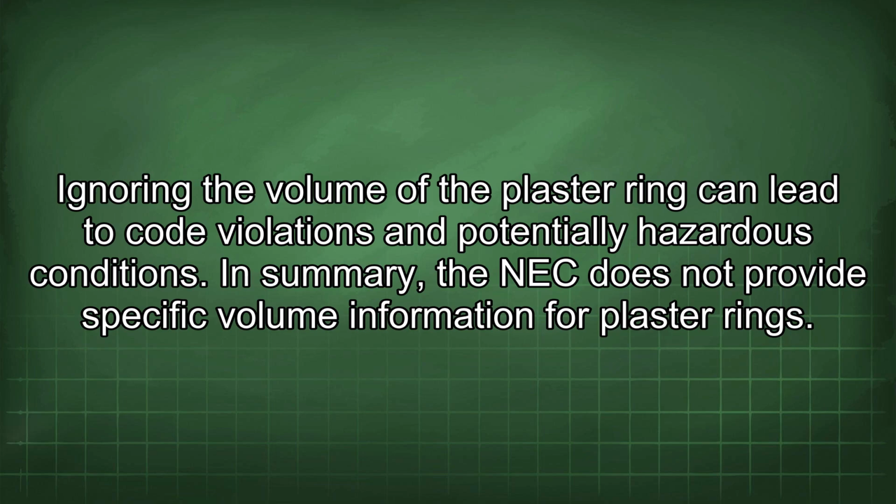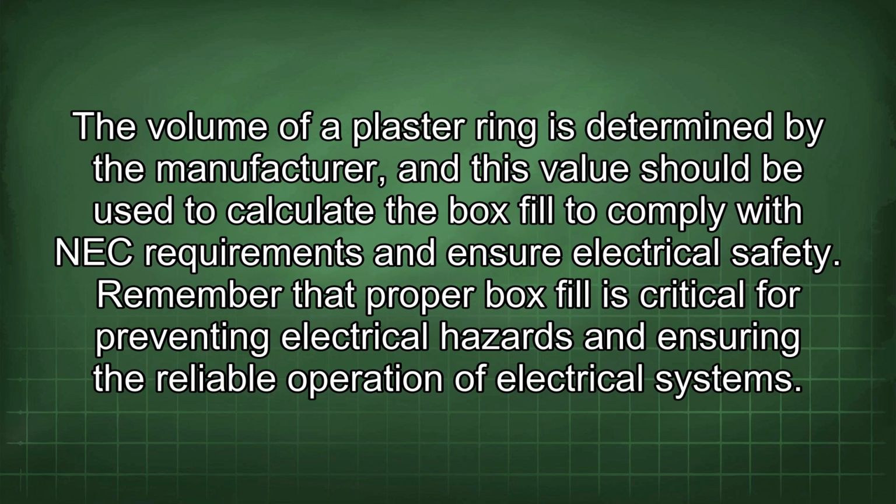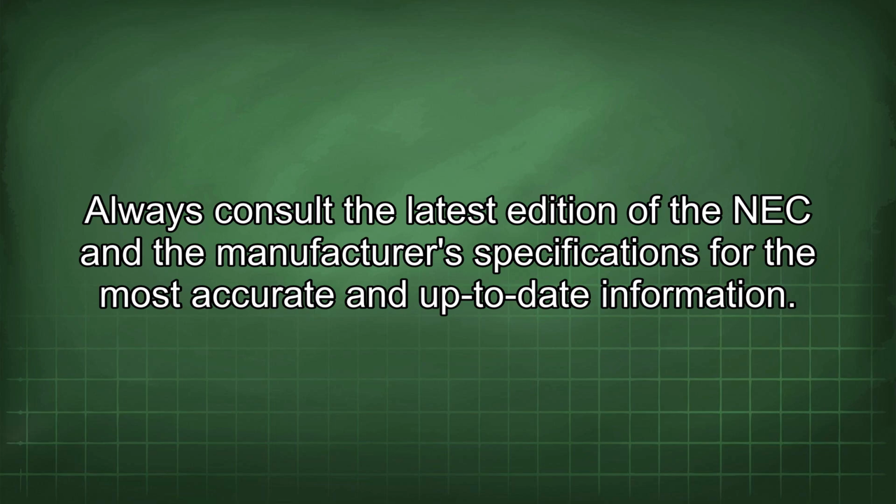In summary, the NEC does not provide specific volume information for plaster rings. The volume of a plaster ring is determined by the manufacturer, and this value should be used to calculate the box fill to comply with NEC requirements and ensure electrical safety. Remember that proper box fill is critical for preventing electrical hazards and ensuring the reliable operation of electrical systems. Always consult the latest edition of the NEC and the manufacturer's specifications for the most accurate and up-to-date information.